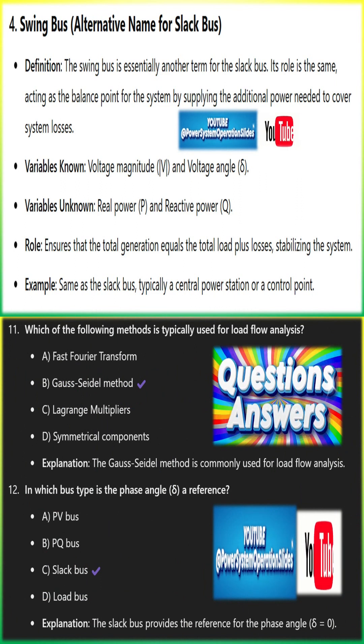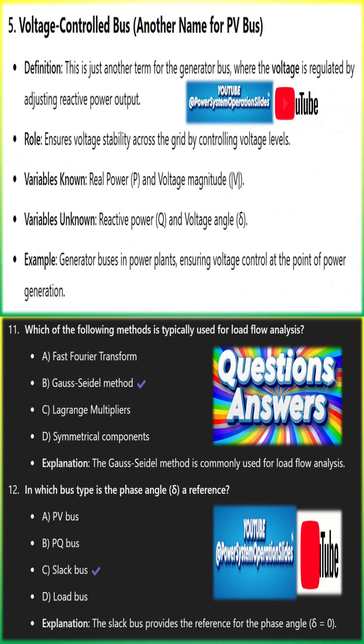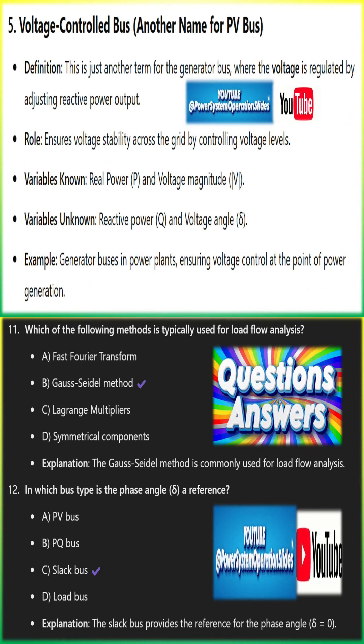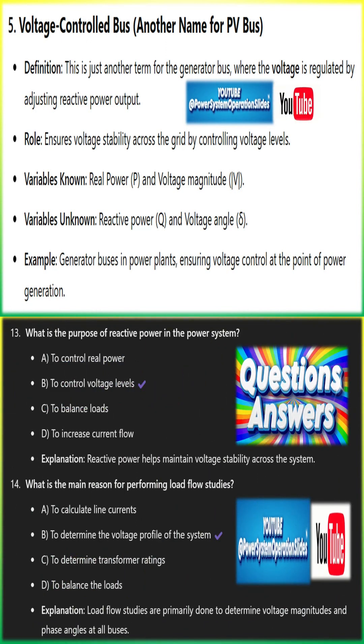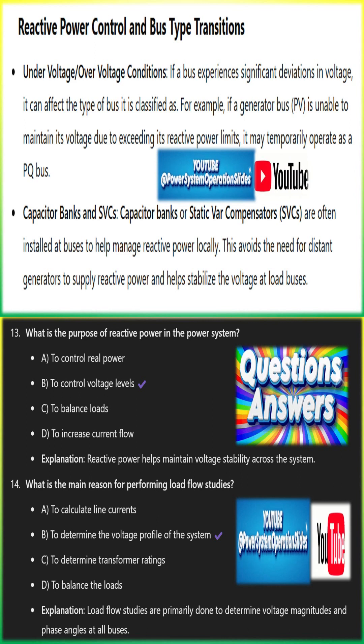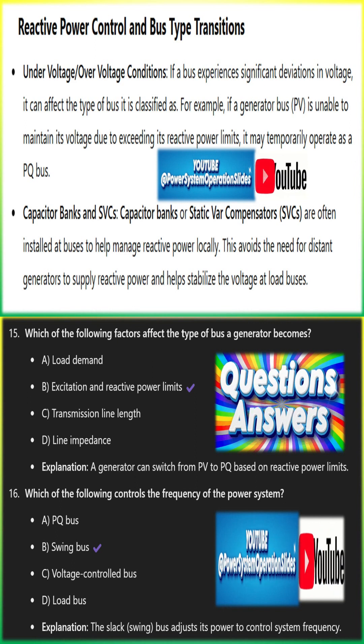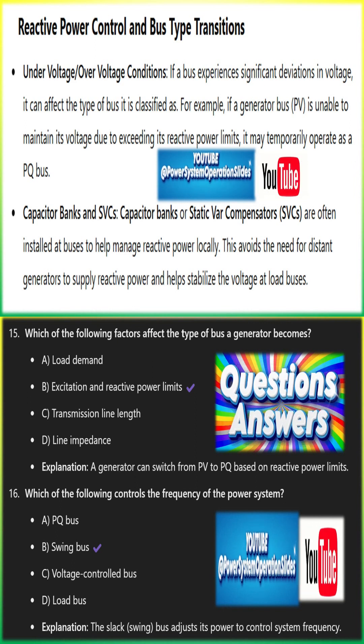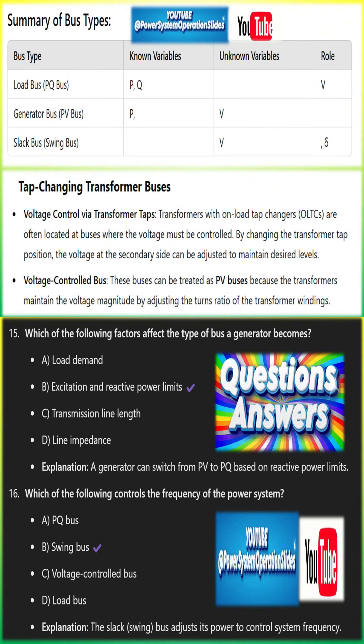Reactive power impact: for certain loads like motors or air conditioners, the power consumed is not purely active real power P, but also reactive Q, which is crucial for maintaining voltage levels. Reactive power management is essential because insufficient reactive power can lead to voltage drops and system instability. Power factor: load buses are often assessed based on their power factor, which is the ratio of real power P to apparent power S. A low power factor indicates a high proportion of reactive power, leading to inefficiencies.